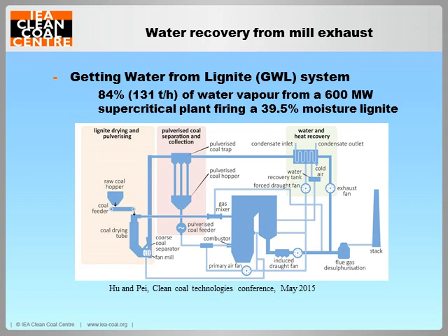And calculations for a 600 megawatt supercritical plant using a version of the system suggest that some 84% of the water vapour in the mill exhaust could be recovered when firing a nearly 40% moisture lignite. And this would be enough to meet the entire water consumption of a dry cooled plant with a wet FGD unit.